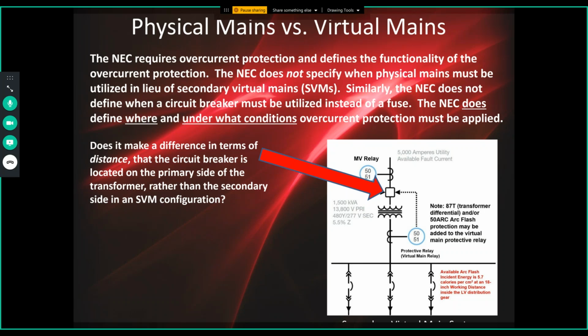Now, again, in order to use a secondary virtual main, you have to have control of the transformer. You have to own the transformer in order to install a primary device. And similarly, as I noted, the NEC doesn't tell you whether you have to use a breaker or a fuse. What the NEC does do is define where and under what conditions overcurrent protection must be applied.